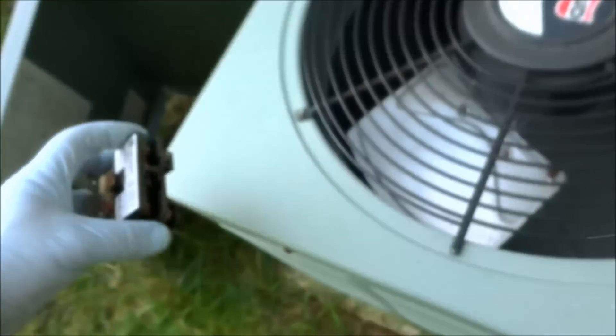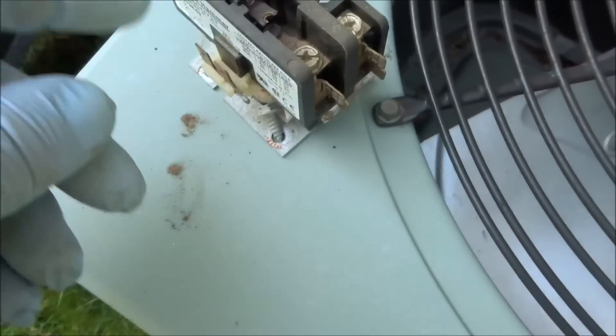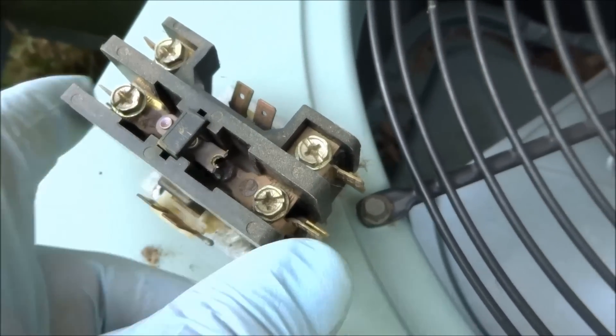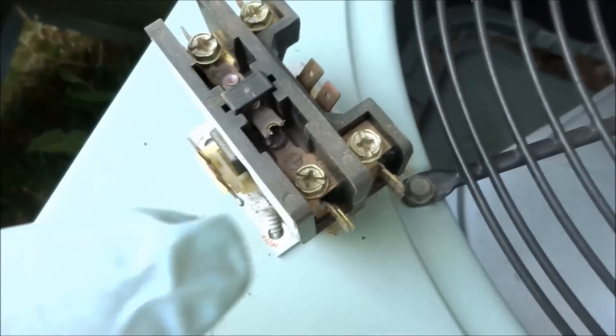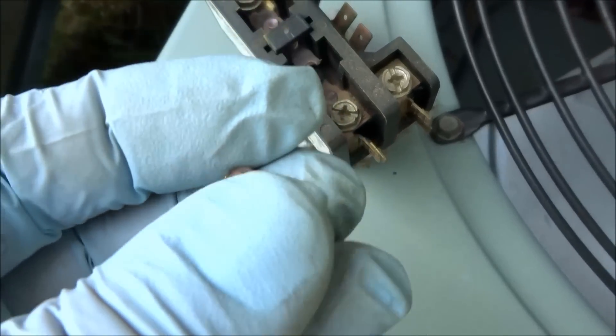You can see the contactor burnt right off. Melted right off. So that thing was, he was complaining about it staying on, not shutting off. Looks like that might be the culprit.